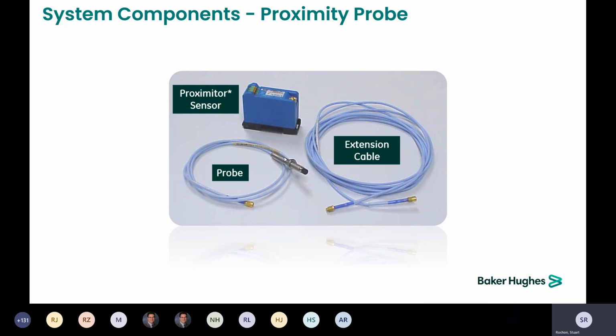They do need to be matched as an electrical length. So the proximeters for the 8 millimeter probes come in either 5 meter or 9 meter without any kind of modification. And that means that the total length of the extension cable and the probe electrically, not necessarily physically, sums up to that 5 meter or 9 meter. So if you have a 5 meter proximeter, you want either a 4 meter extension cable and a 1 meter probe, or a 4.5 meter extension cable and a 0.5 meter probe. Same thing goes for your 9 meter. As long as the total of the extension cable and the probe add up to the total length of the proximeter, you should be okay.